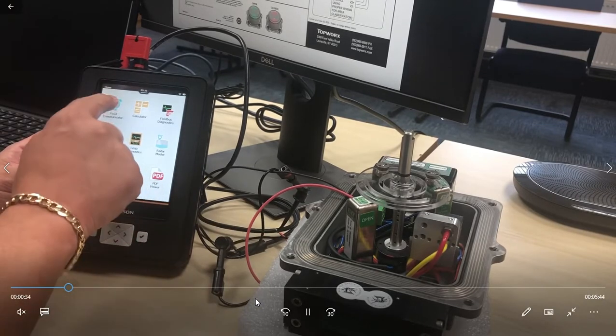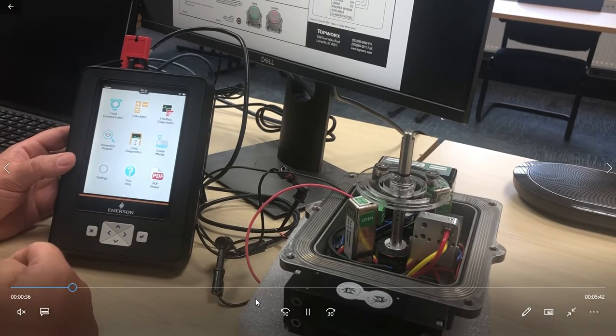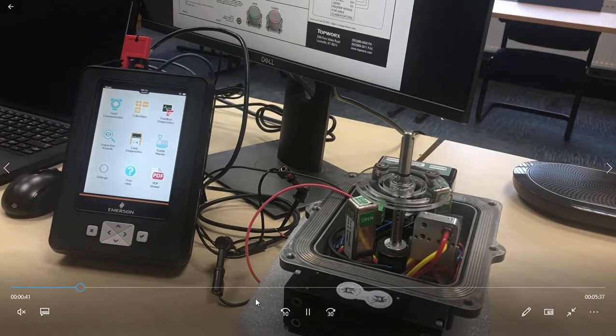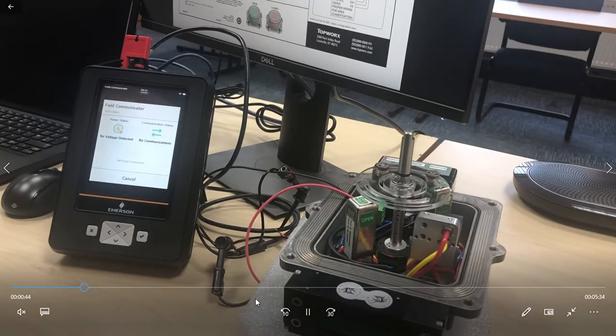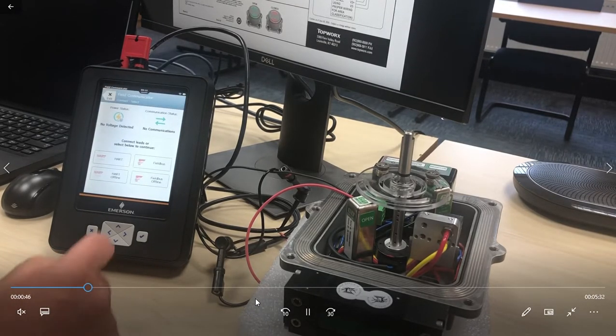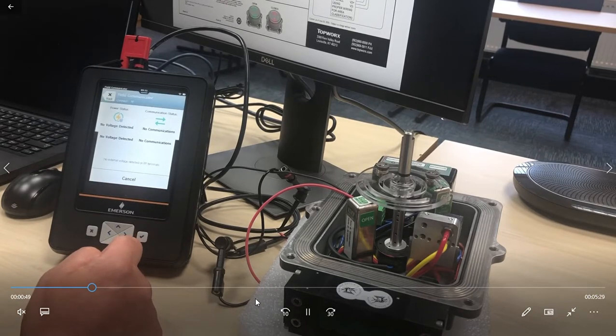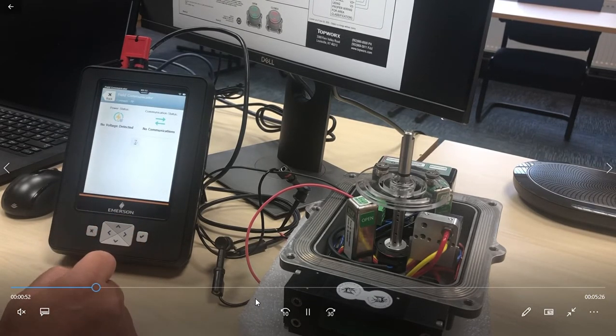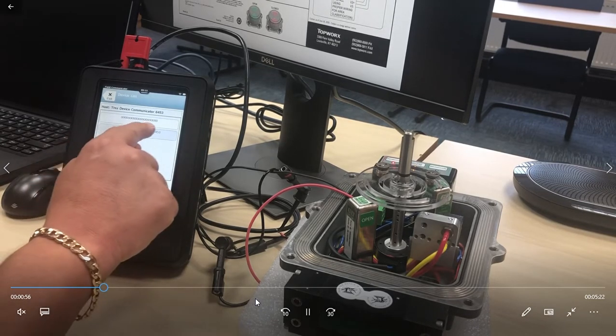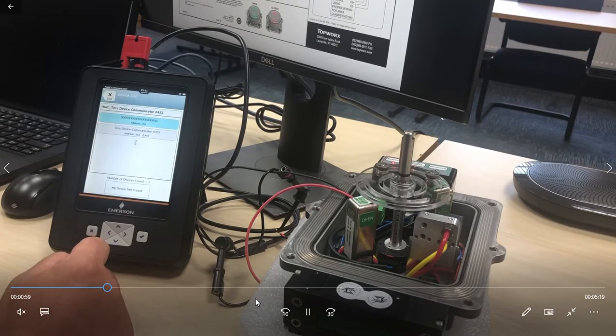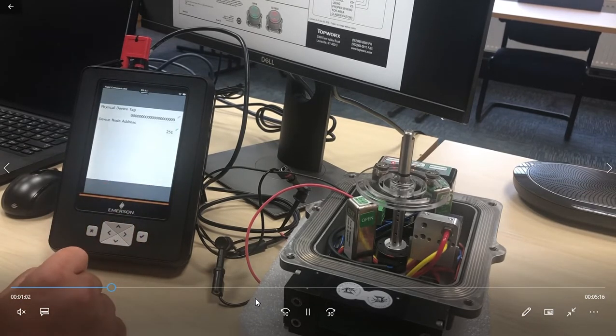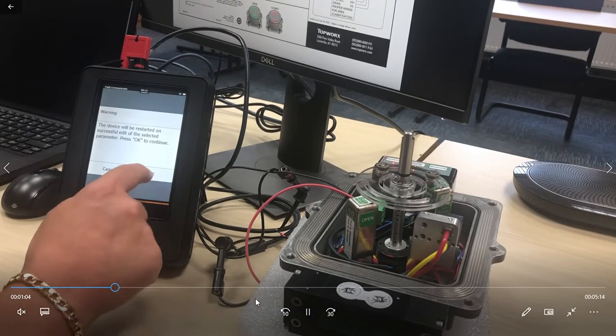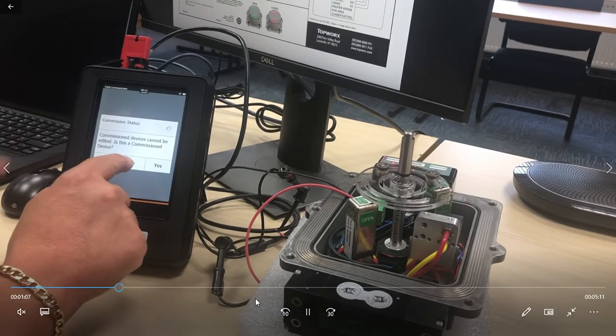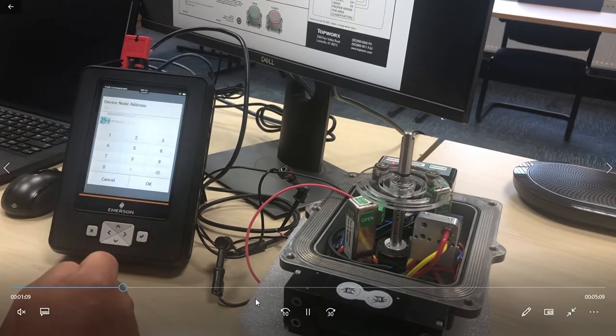Now we're going to initiate the field communicator device application on the TREX. We're selecting Fieldbus and we're also selecting powered from the TREX. When you initiate it, first of all, you'll notice that the address is 251. This is a temporary address that has to be changed. In this instance, we're changing it to the number 34.